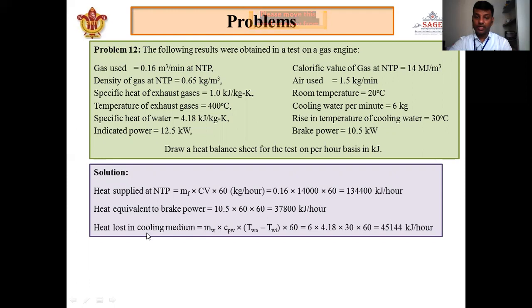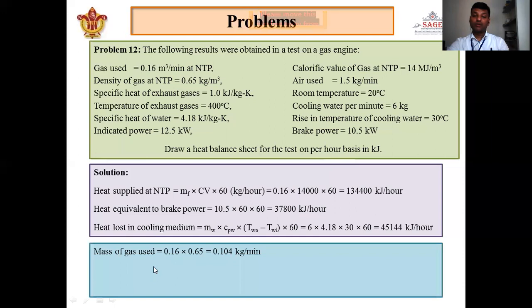Heat lost in the cooling medium: Q = m × Cp × ΔT. Mass flow of water m = 6 kg/min, Cp = 4.18 kJ/kg·K, rise in temperature ΔT = 30°C. This gives a result in kJ/min, which we multiply by 60 to convert to kJ/hour. The heat lost to the cooling medium is 45,144 kJ/hour.